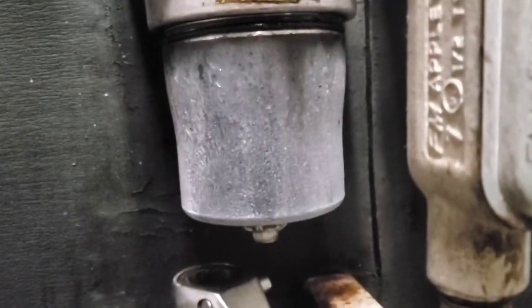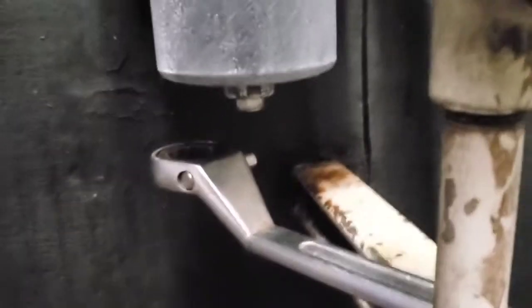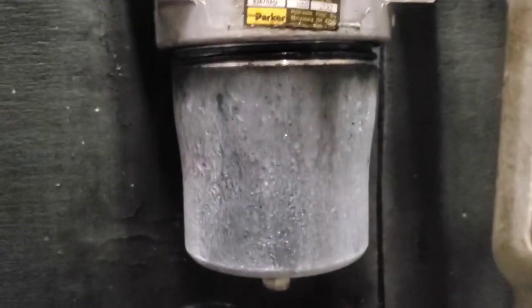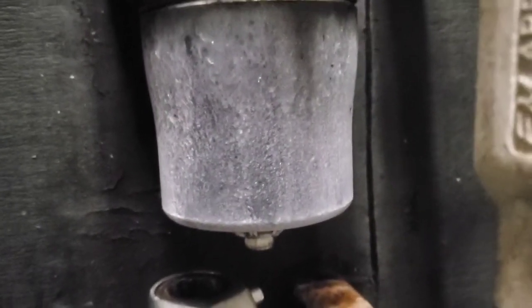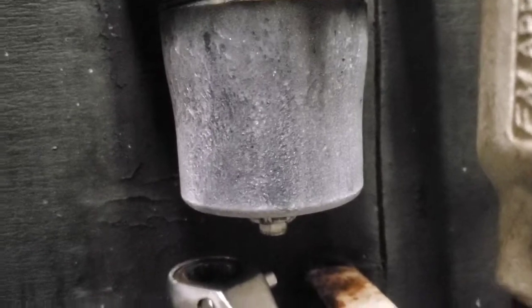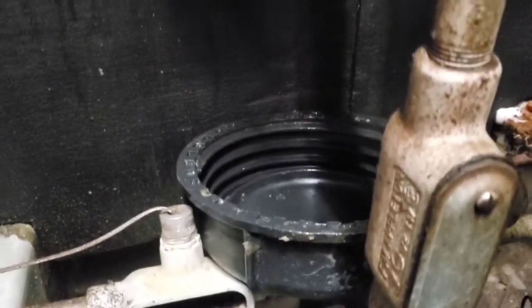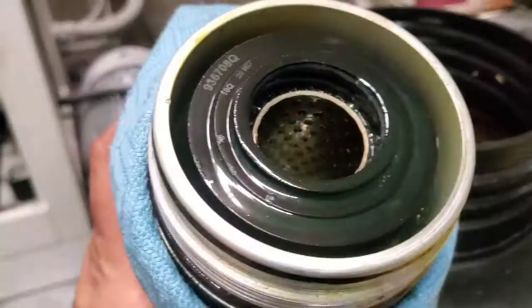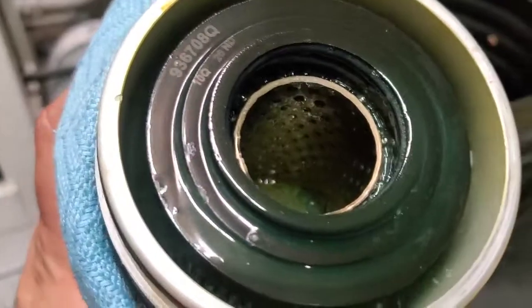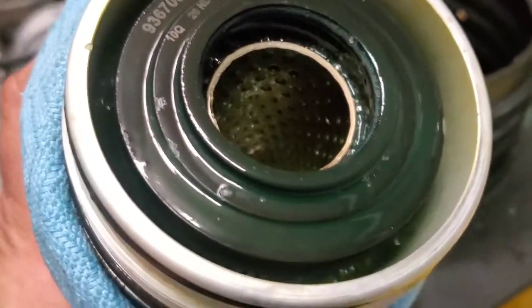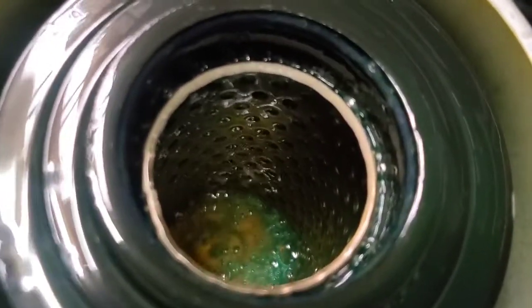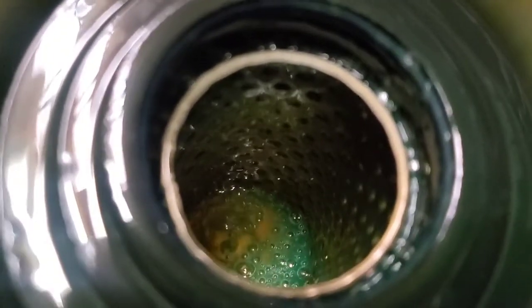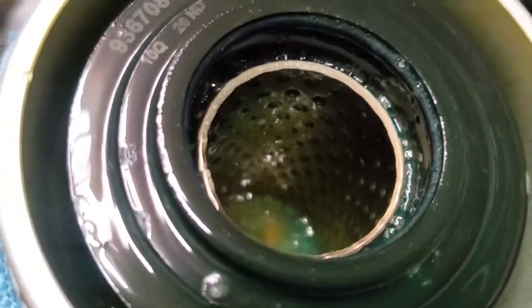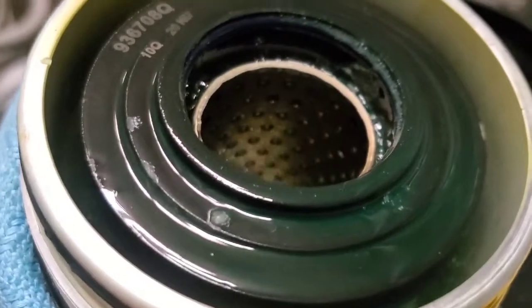All right, so we're using this wrench on that nut right there to back that whole oil canister out. And that frost that you see is a little bit of liquid refrigerant that's boiling off. When we do that, oil is going to start dripping out of it because this is the lowest point in the system, and we're going to catch it in that little catch can. All right, so here's what the inside of the canister looks like. You've got a filter element in there, and we've got some oil still in there with some refrigerant that's bubbling out. It's boiling off. We're going to replace this oil filter element.